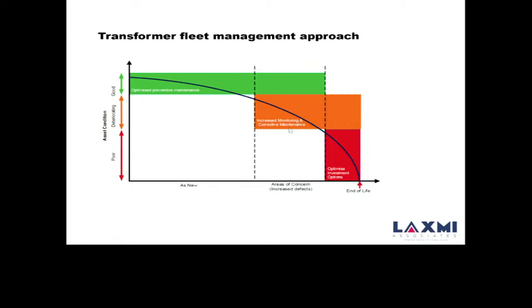So what is the benefit? Suppose this is a life cycle: till the mid-life, the transformer normally behaves well and covers the green zone, then goes into increased monitoring and corrective maintenance, and then into the red zone where you need an optimized decision—whether to refurbish, rewind, or scrap it. But if health index is done in the green zone itself, you have enough buffer time, 10 or 15 years, to decide what you want to do for the rest of the transformer's life.